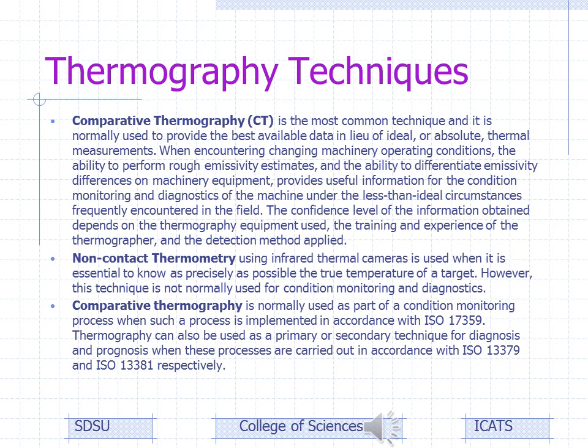Again, more scientific level here, because you're going to know the emissivity, and emissivity becomes very critical at that point to knowing what it is. You're usually going to use a fixed camera. You'll find that in several of our labs here, and a very tightly controlled temperature for that environment, so you're getting the same image. You can consistently depend on that data for what you're looking at.